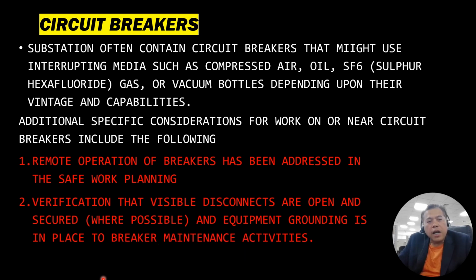Number one, remote operations have been addressed in the safe work planning. Number two, verification that visible disconnects are open and secured where possible, and equipment grounding is in place, breaker maintenance. So this is very crucial. We need to verify our earthing, especially when you start to energize our equipment and the substation as well. It is very dangerous and you need to verify all this. Okay, grounding.